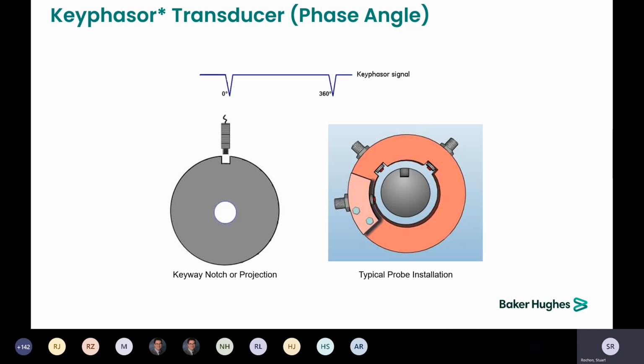We also use proximity probes as a Keyphasor. This gives us a once per revolution marker point, and having that marker point recorded, and the angle at which the probe is installed, and the angles at which the X and Y probes are installed, is necessary for doing proper diagnostics and also for doing proper balancing.